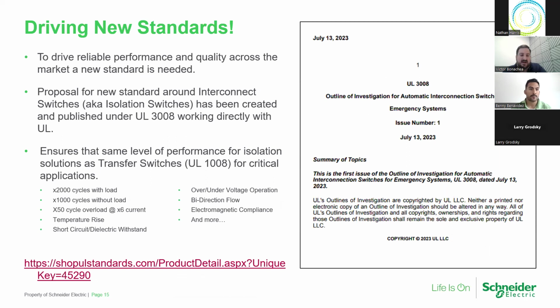Now, the thing is the concept of isolation switches and interconnection switches are relatively new concepts out there as microgrids are evolving and the need for these types of isolation devices are forming out there. And there was actually no standard out there. As we mentioned, if you're going to use them for emergency standby, they have to be listed. Well, there was no existing standard, and because there was no existing standard, it was difficult to get any sort of UL approval on them if you don't have a standard to list against. So UL, in partnership with Schneider, actually developed a new standard known as UL 3008, which is for automatic interconnection switches, as we call it.